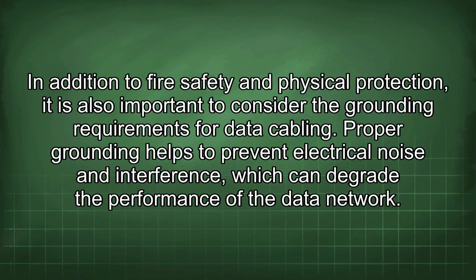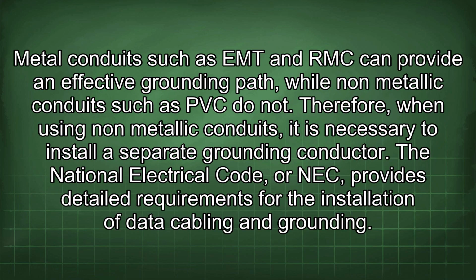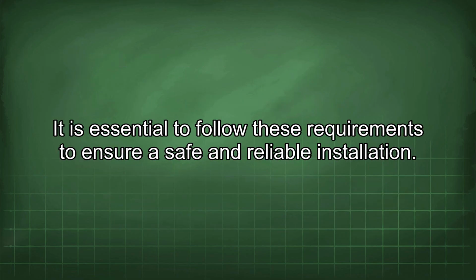In addition to fire safety and physical protection, it is also important to consider the grounding requirements for data cabling. Proper grounding helps to prevent electrical noise and interference, which can degrade the performance of the data network. Metal conduits such as EMT and RMC can provide an effective grounding path, while non-metallic conduits such as PVC do not. Therefore, when using non-metallic conduits, it is necessary to install a separate grounding conductor. The National Electrical Code, or NEC, provides detailed requirements for the installation of data cabling and grounding. It is essential to follow these requirements to ensure a safe and reliable installation.